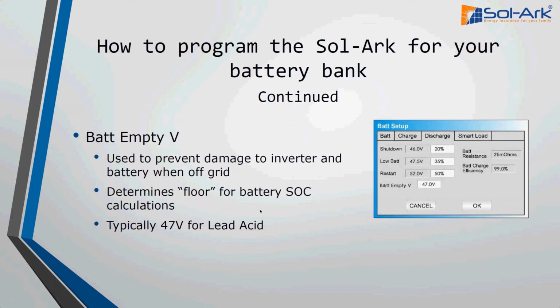But this empty voltage also determines the floor for our state of charge calculations. So if the system thinks you're at 20%, but then you hit the battery empty voltage, we're going to redefine how much energy was taken out of the battery to be the full battery's capacity, and this helps us get the SOC more and more accurate over time with our learning algorithm. And then the default value here, just so you guys know, is 47 volts.